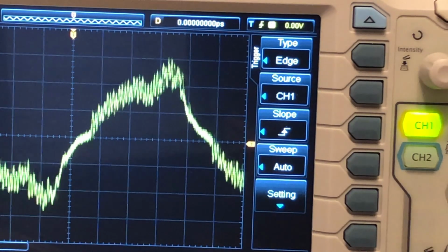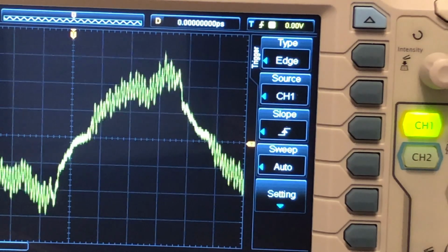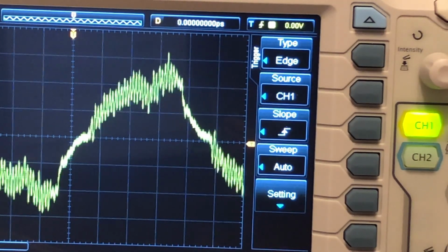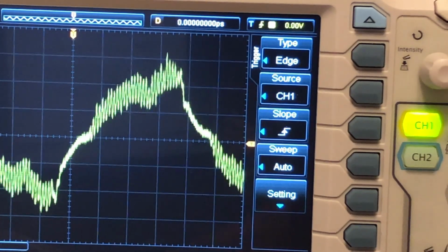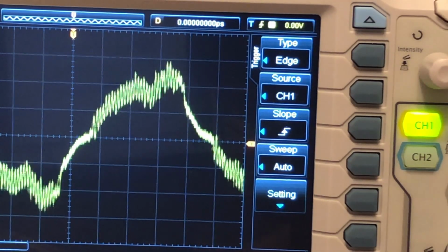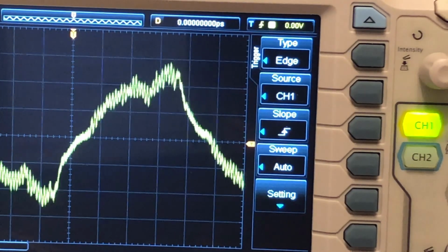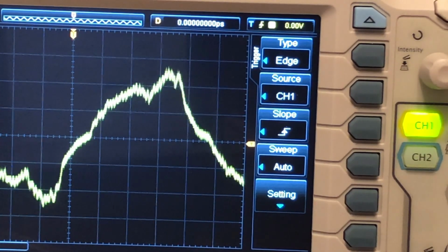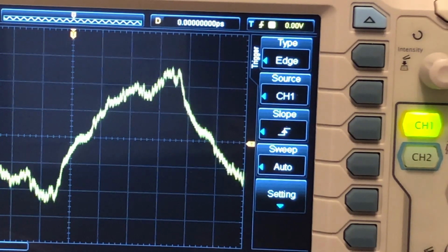Okay, trigger level. When the trigger source is an analog channel, trigger occurs only when the signal reaches the preset trigger level. You can modify the level using trigger level at this point. An orange trigger level line and the trigger mark appear on the screen and move up and down with rotation of the knob. The trigger value, such as trigger level 164 millivolts, at the lower left corner on the screen also changes accordingly. When stopping turning the knob, the trigger level disappears in about 2 seconds.